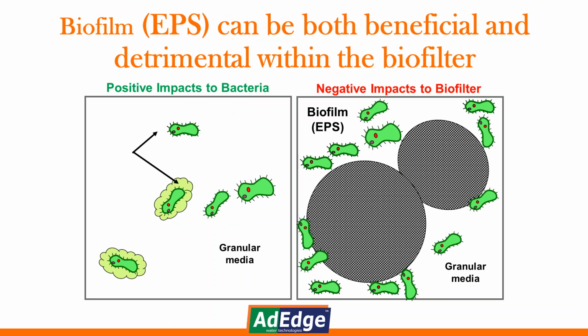And so here's another example of just some of the biofilm, and on the left, you can see there's a small amount of biofilm. It helps protect the bacteria. Whereas on the right, you can see a little bit larger masses in there, and those then begin to plug the activated carbon and plug some of the sites, creating a premature pressure differential. So again, you've got the protection, the adhesion there. On the right side, it starts causing head loss when you have too much, and you can actually have some clogging occur.